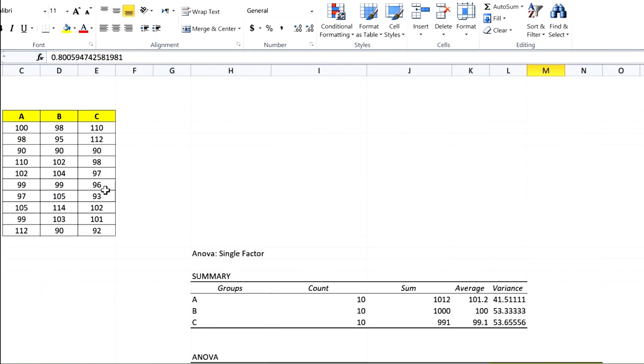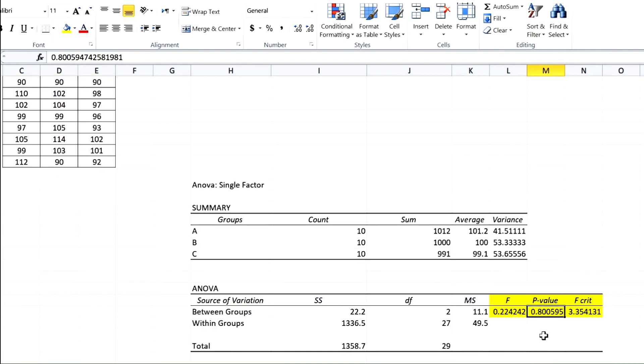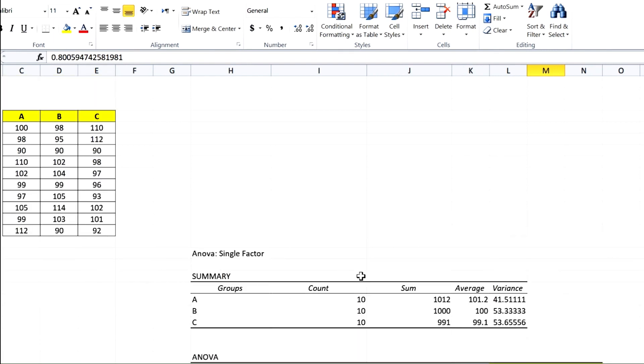This means if you have two instruments in your lab and you buy a new one and want to check its performance, you analyze replicates of samples at a known concentration. If you find no significant difference, all of these instruments can be used to analyze the target analytes and get accurate and reliable results — their performance is equal.